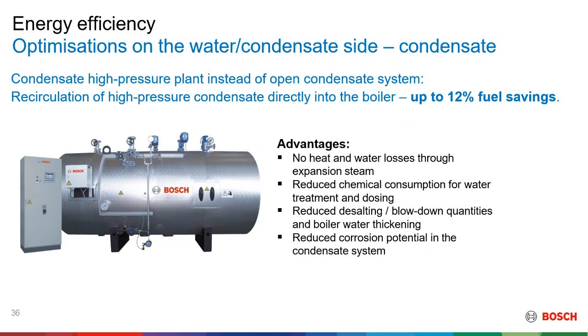So there are two types of condensate tanks. They're usually the open air, which is not really advisable because if you have an open air condensate tank, you're actually losing a lot when it comes to flush them. So a fully cladded condensate tank is usually advised. Here you reduce the amount of losses in terms of water and heat, the amount of chemicals that you're consuming when it comes to treating the water. And by reducing the amount of chemicals, you're also reducing the amount of blowdowns, or how many times the boiler has to desalt. And thereby, just by having good quality water, you also reduce the corrosion potential of the system.